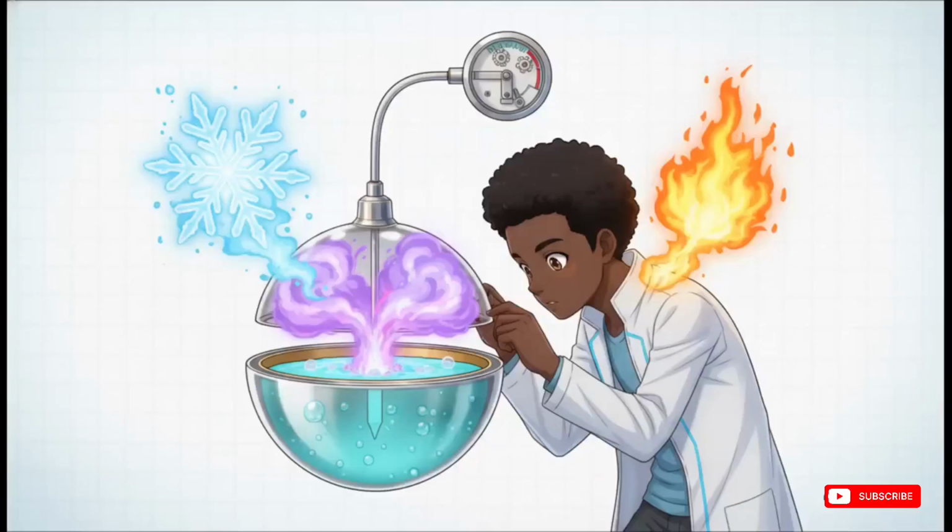A vapor-actuated thermometer operates strictly on the principle that every liquid has a specific vapor pressure for any given temperature. The pressure in the entire system depends entirely on the temperature at the free surface of the liquid inside the bulb. Because of this, you can choose very specific filling media to achieve really broad operational ranges. We're talking anywhere from -50 degrees all the way up to 600 degrees Fahrenheit.